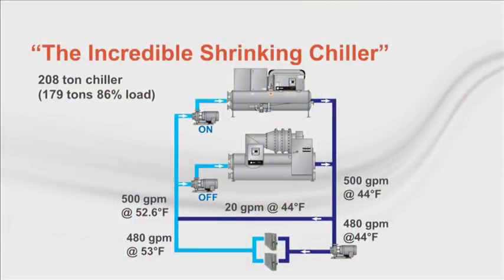So let's start sleuthing. For this one, we'll pick a spot in the sequence just before the second chiller has to come on. The same system now has the building demanding 480 GPM at 44 degrees. We are just nearly balanced, only 20 GPM in the decoupler pipe. Now suppose we only get a 9-degree DeltaT in the loads, when we expected 10. When you purchased that 208-ton chiller, you thought that's what you were getting. Nope. You really got a 500 GPM chiller.